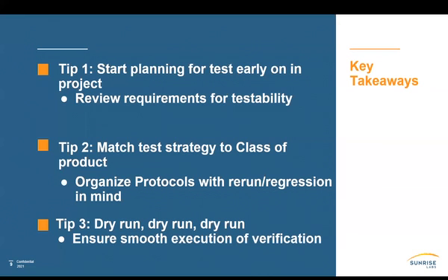And last, dry run, dry run, dry run. Can't emphasize enough the power of testing early, testing often. I know it's a cliche, but it's very true. Get through your tests, test your system and your software as much as possible. You want to ensure a smooth execution of your verification. And please also remember that verification activities include all members of the development team and not just your test engineers.